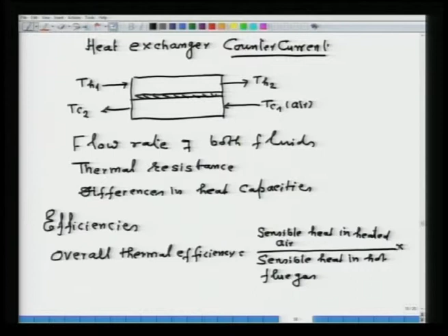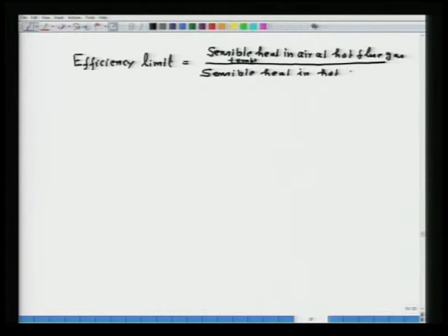Now, in this particular definition, it is inbuilt that air can be heated above the temperature of the hot fluid, which is thermodynamically not possible. Therefore, another limit is defined, called the efficiency limit. The efficiency limit is defined as the sensible heat in air at hot flue gas temperature, which is the maximum you can get, divided by the sensible heat in hot flue gas. Of course, you have to multiply by 100 to get the percentage.